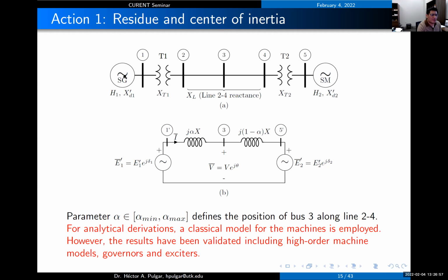Because you have a reactance in the generator and in the transformer, at bus 2 we will have some reactance. Since we just have a reactance in the system, we have a total reactance X, and I use a coefficient alpha to indicate at what point along this line we're located. Alpha has a minimum value because we need to consider the reactance of the generator and transformer, but if I start increasing alpha, I move along this line.